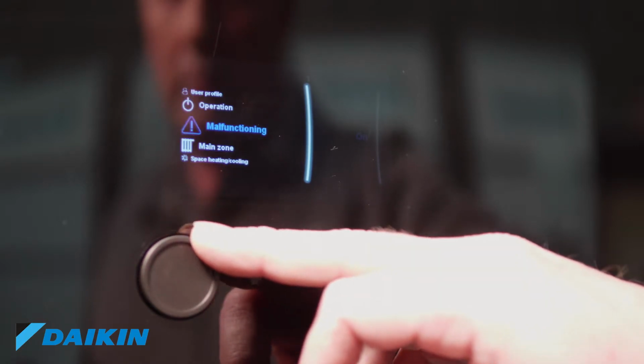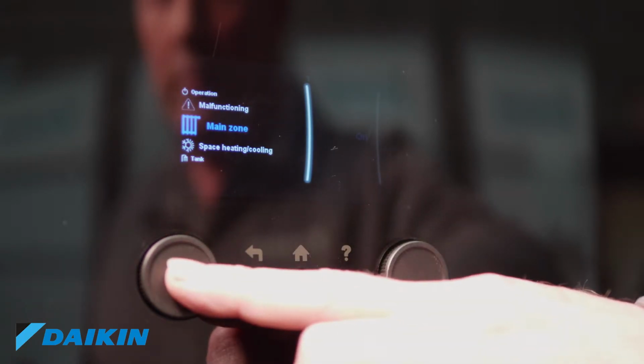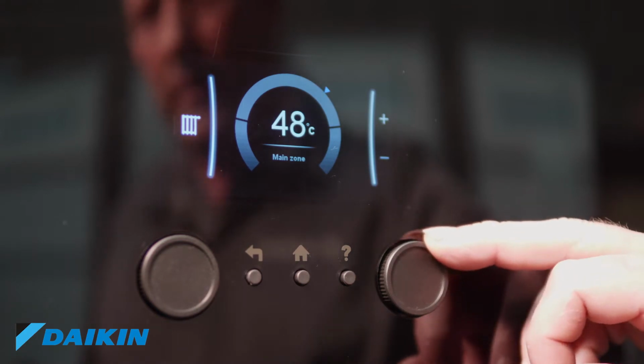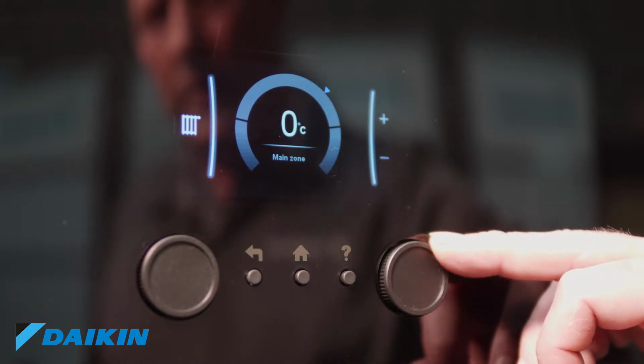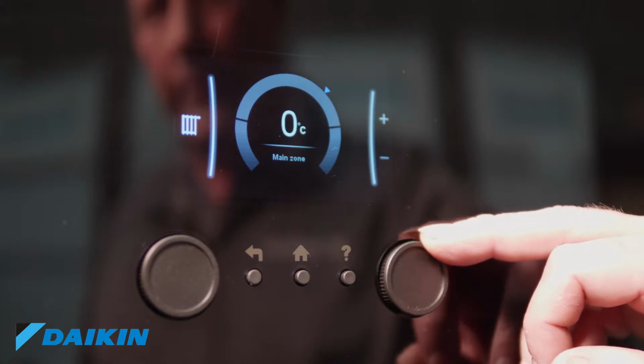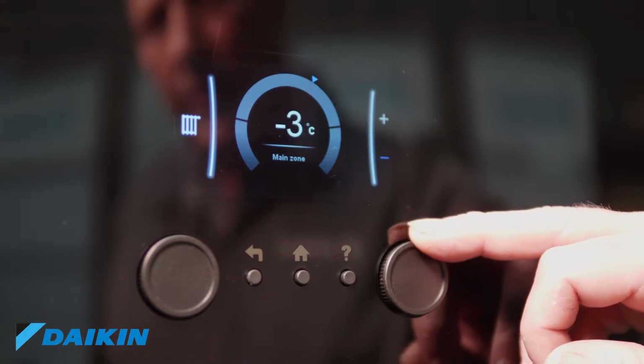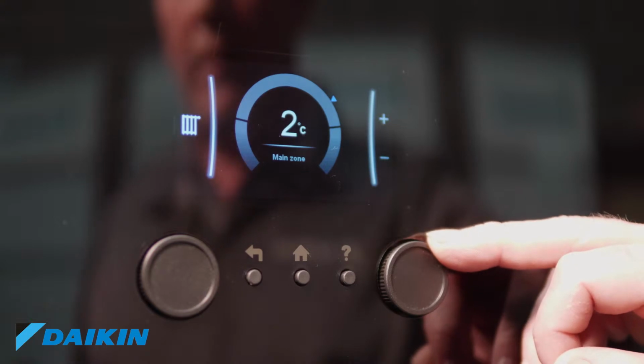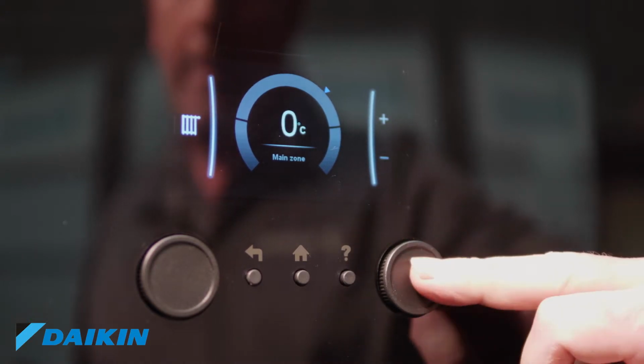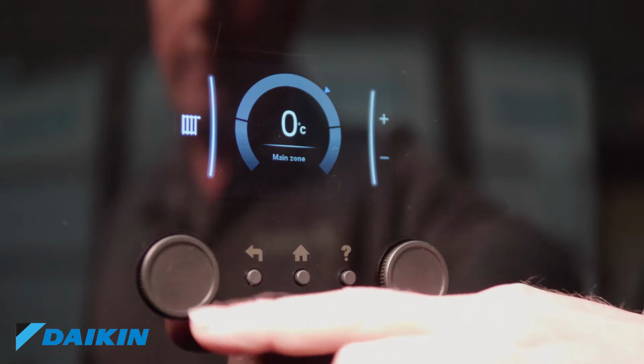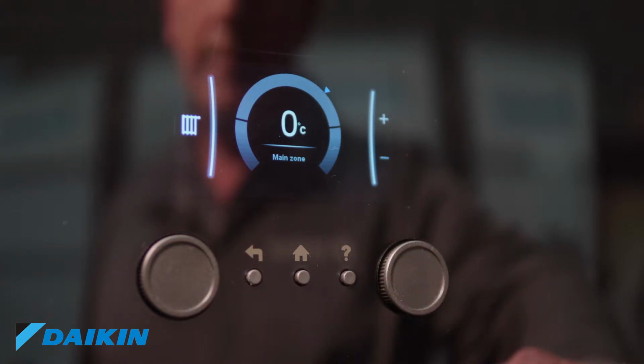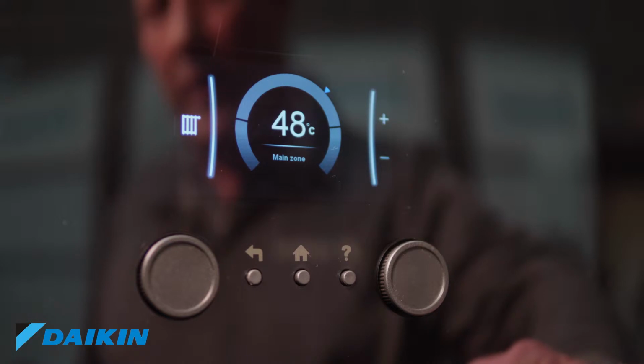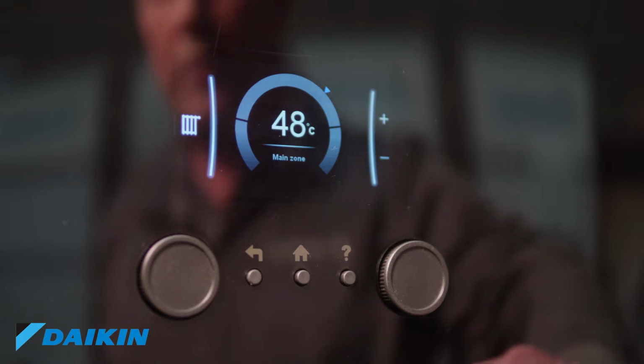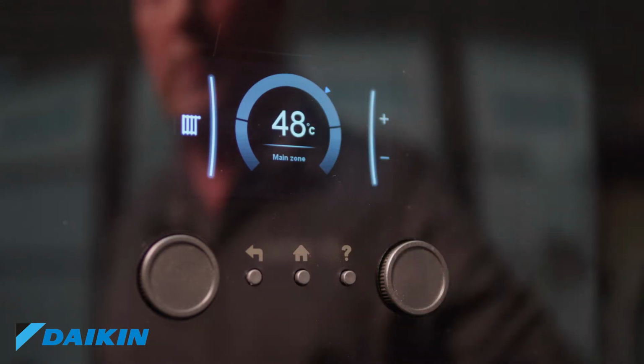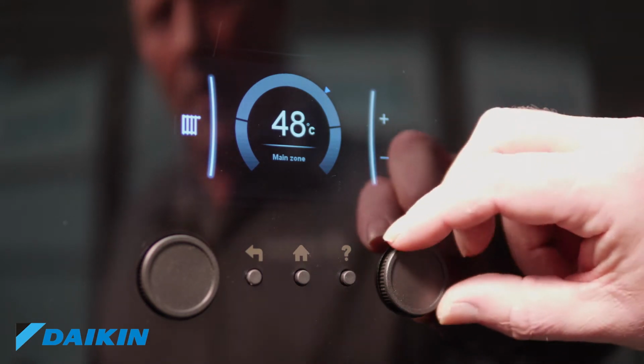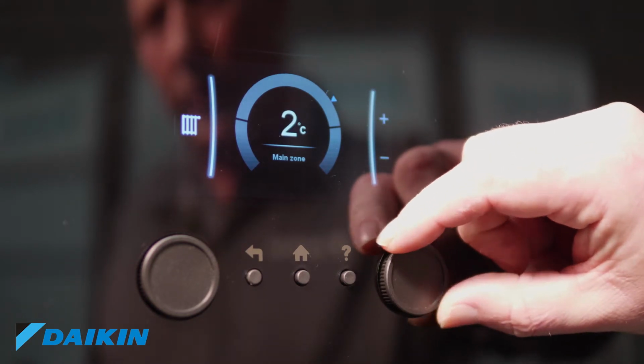If we now scroll to our main heating zone and we click, we can now select a temperature. Now as we did in the setup, we set this for weather compensation, so we have the ability to alter the offset of the graph. We just wait for that to come back. Based on the graph that we set and the current outdoor temperature, the machine is calculating a temperature of 48 degrees.